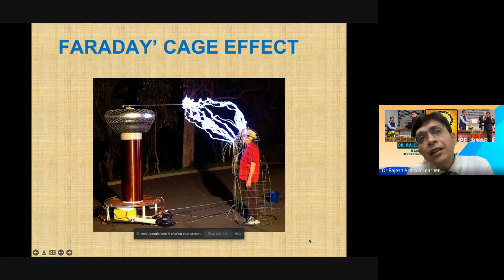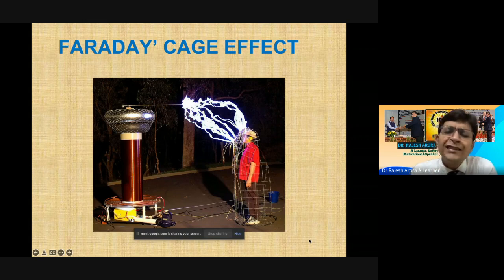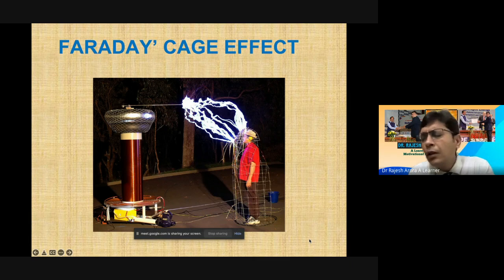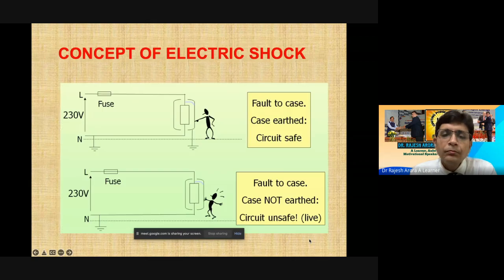To avoid that, what happens? We design our lightning protection system based on IS 2309, which has already been obsoleted and is now guided by IEC 62305 part 1 to part 4, and we have to do the risk assessment as per 62305 part 2, and based on that we have to choose accurate SPD. The same requirement is also given in the IS and regulations. This is the electric shock I have already explained.